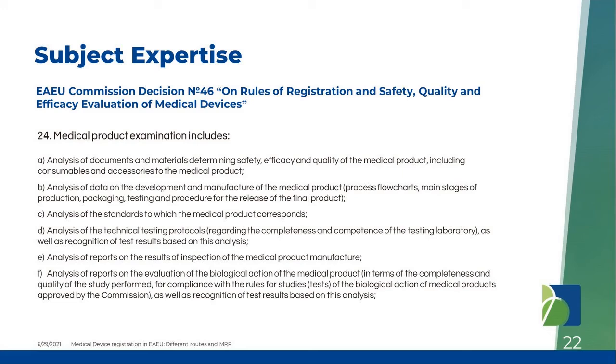I would like to mention that there are no direct requirements to provide R&D documentation, but you should explain how the device works, the principle of action. And you see the point E here. Yes, analysis of reports on the results of inspection of the medical products manufacturer.